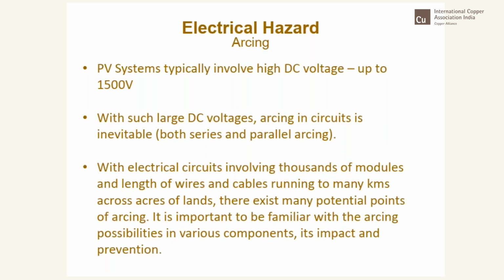So any connection which is loose, or if the insulation has gone bad, they are all potential sources of arcing. So they need to be identified and it needs to be prevented. Obviously, it is not possible to ensure 100%, but that is why high alert is required, especially in an electrical system like a PV system.